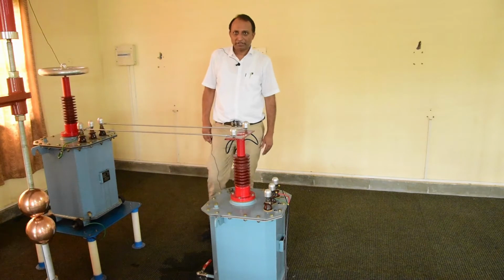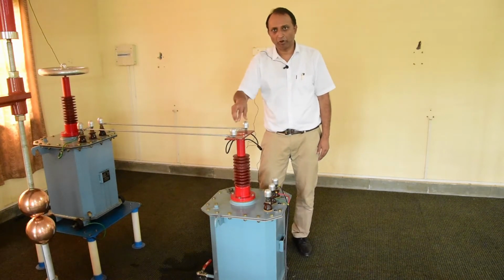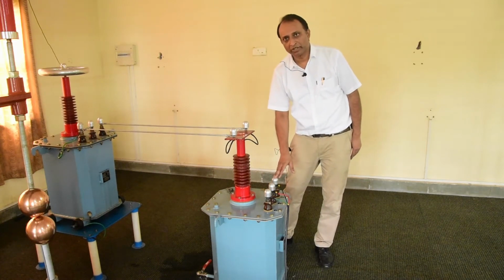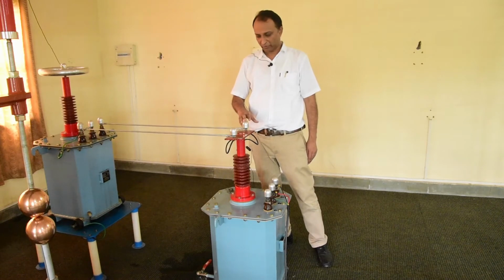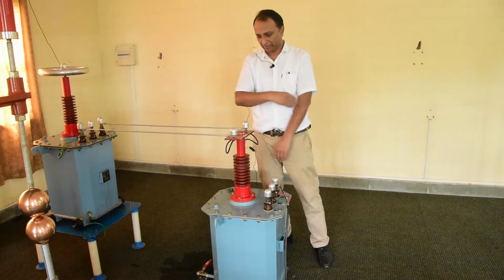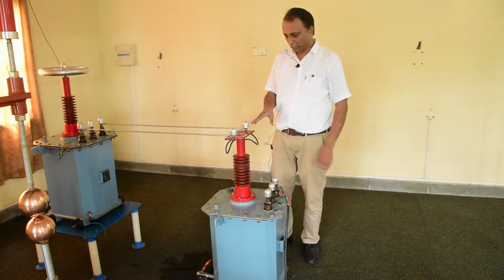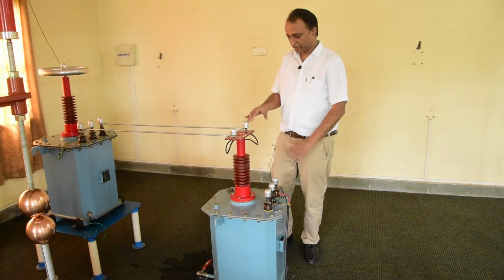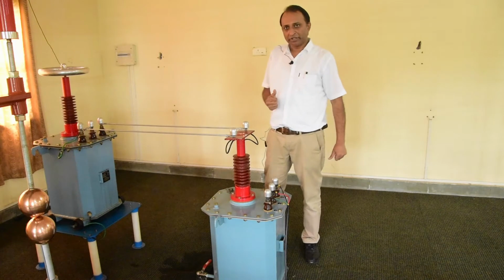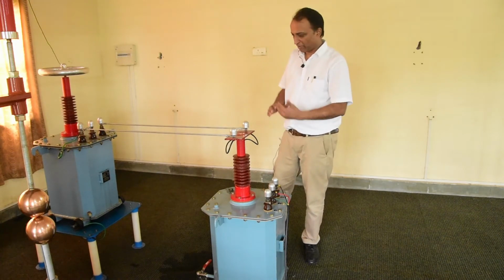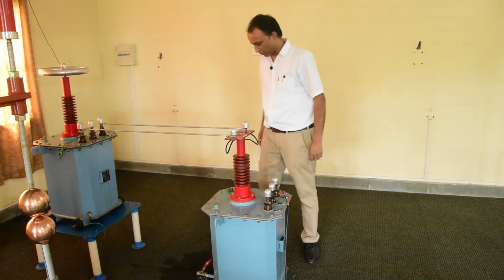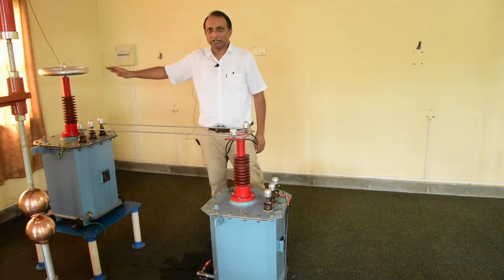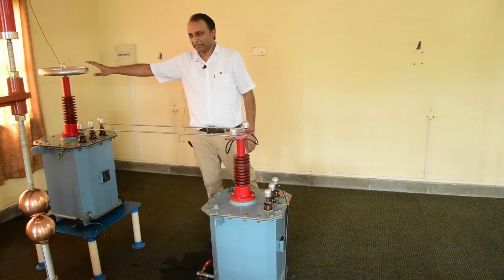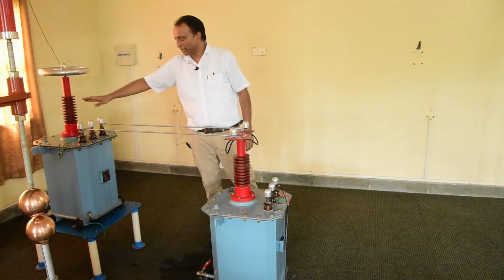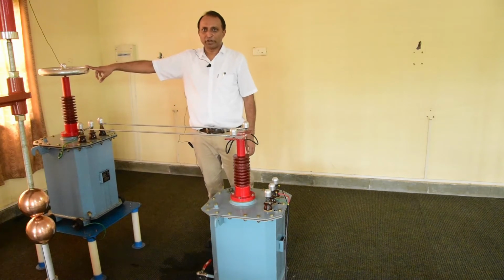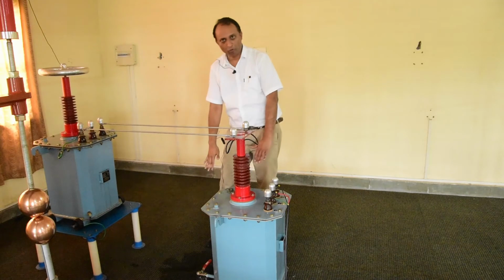Now apart from this, kindly note that all the terminal leads which are brought out of this high voltage step up transformer have spherical caps mounted on them in order to have a uniform electric field distribution. This being a high voltage terminal, the corona discharges or ionization phenomena can be minimized while the testing happens with respect to these transformers. Similarly, here on the 100 kV output side, the final voltage that will be coming, this is a transformer bushing. Here we are going to get the net voltage of 100 kV with respect to the ground potential.